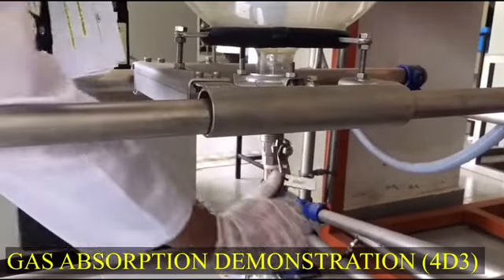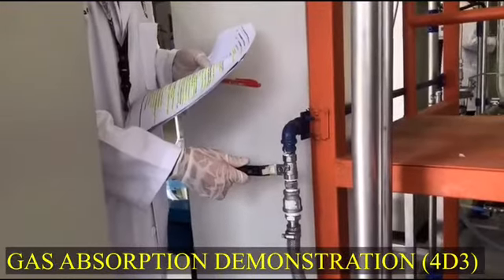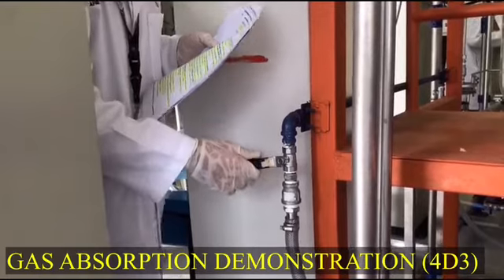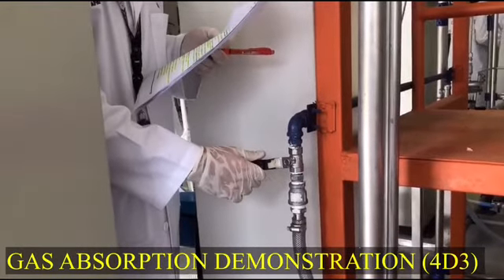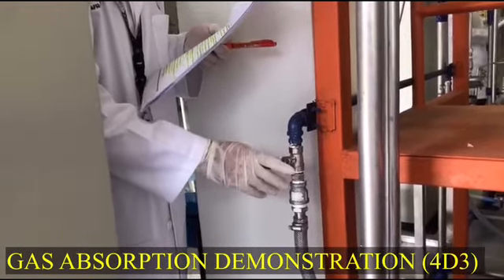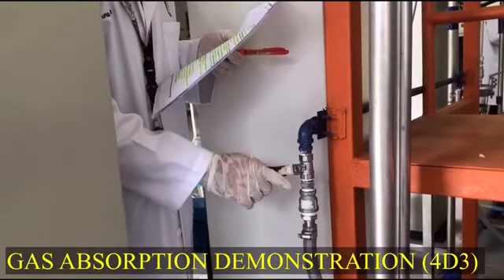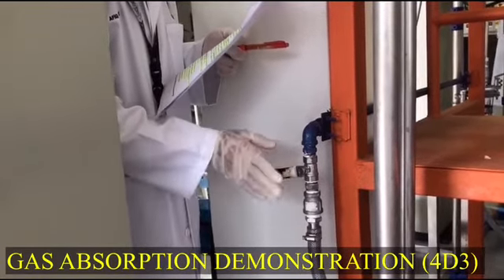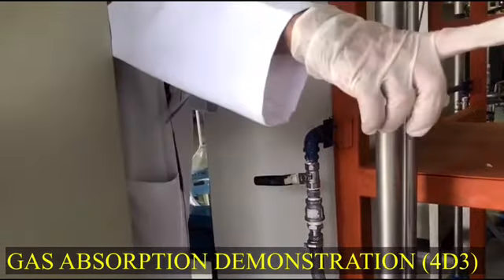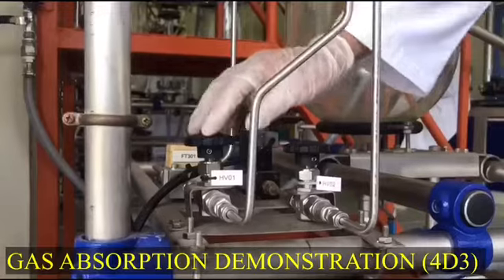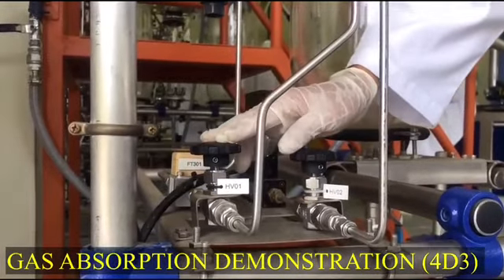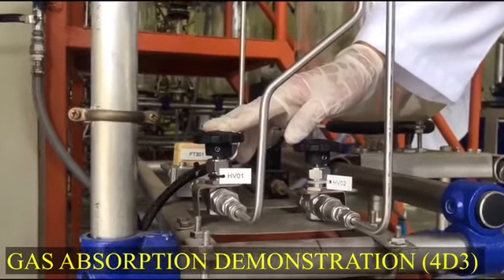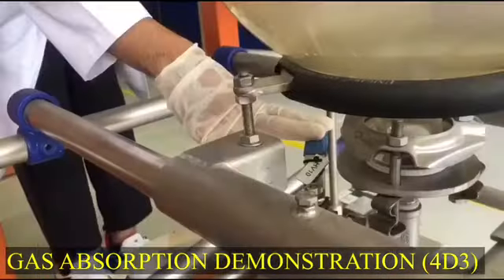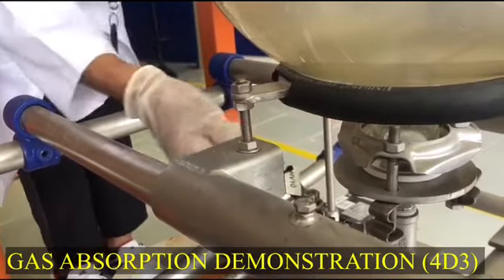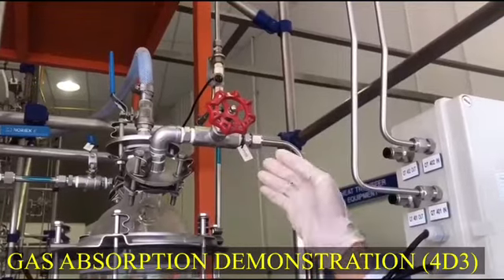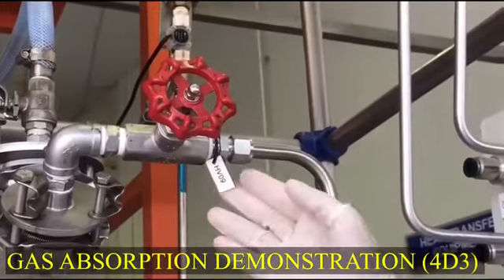V7 open. Open valve water supply to fill feed tank B1 with 30 litre of water. Note, ensure the water level of feed tank B1 is maintained at about 30 to 35 litre by adjusting the valve water supply or valve HV08 if necessary. Open and adjust valve HV01 air supply to give a flow rate of 30 litre per minute. Fully open valve HV10. Slightly open valve HV9, already setting.